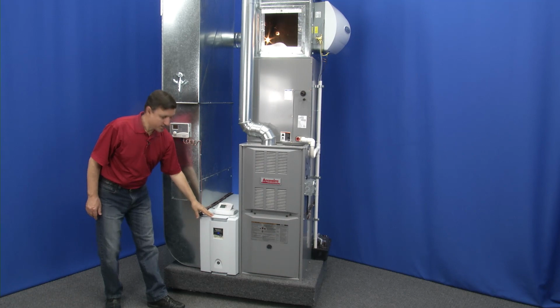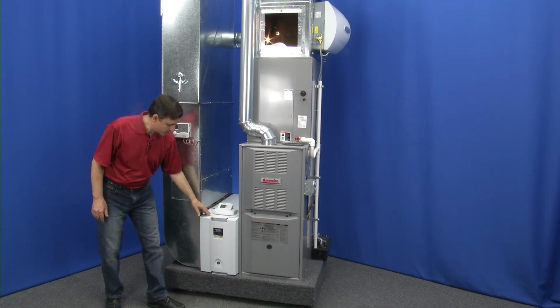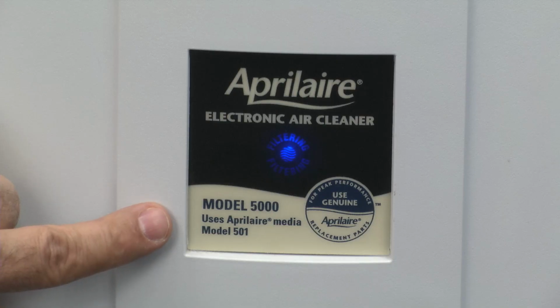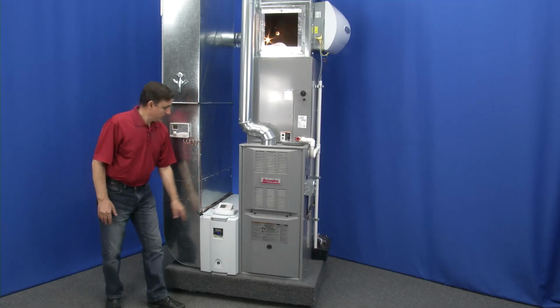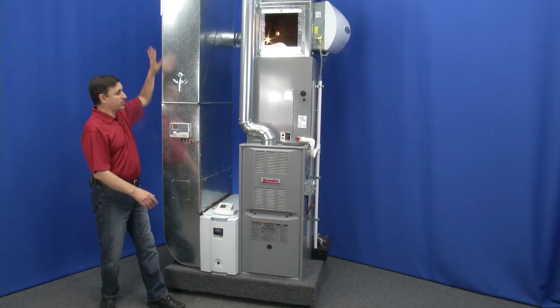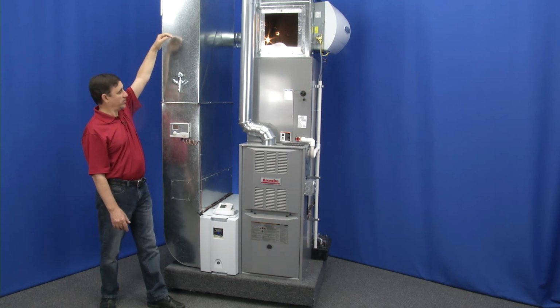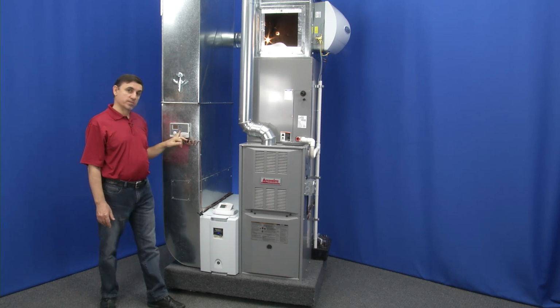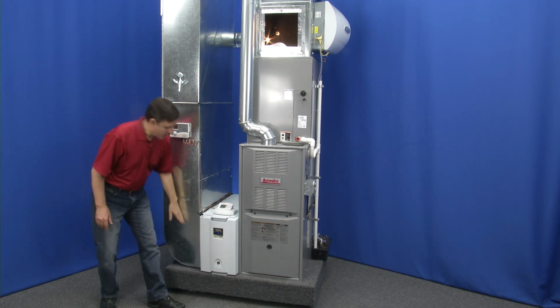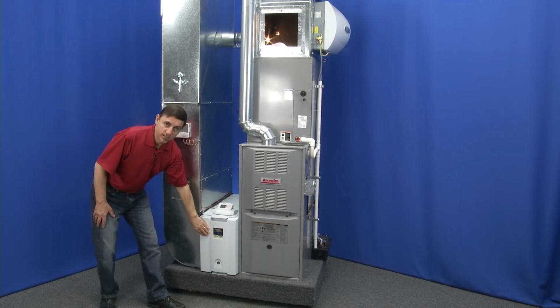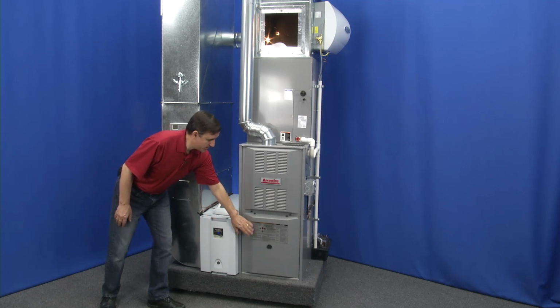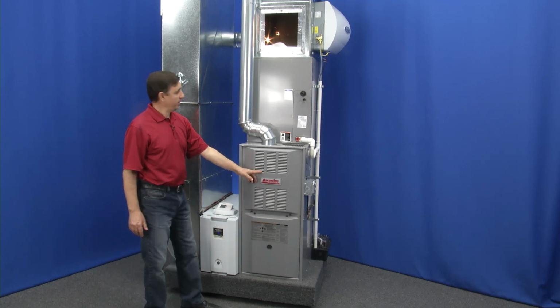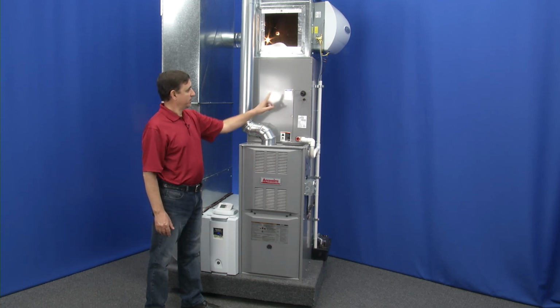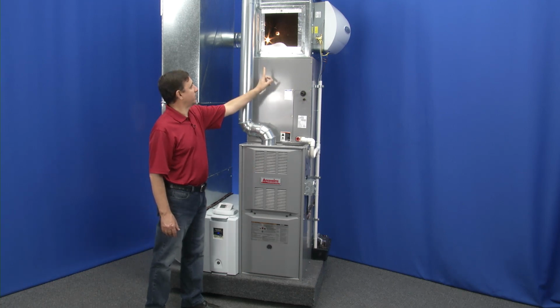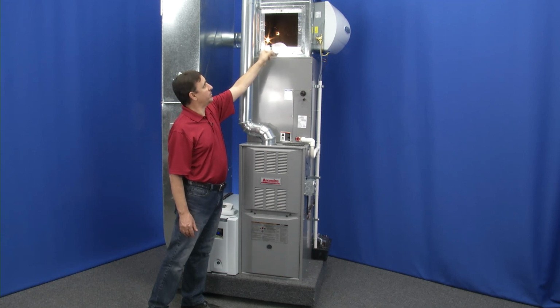The air cleaner here happens to be an AprilAire 5000 air cleaner. If you look closely at the front, you'll see it mentions the model number here. So the air comes from your home through the return air grill, down the return air duct, happens to pass the humidistat, goes through the air cleaner, gets cleaned, goes into the furnace, gets heated in the wintertime or cooled in the summertime, comes up into the supply plenum, and gets blown back into your home.